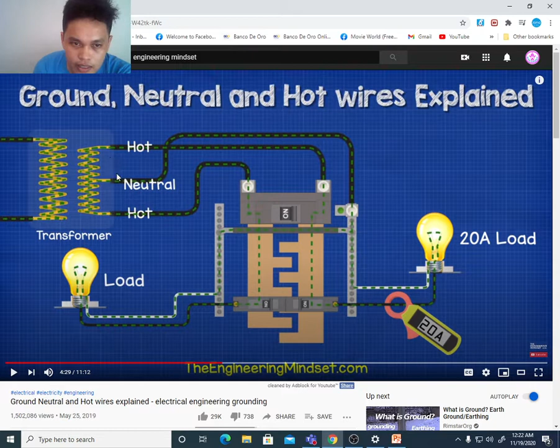Let's say it is, mamaya may example to. So ang purpose ng neutral under normal condition, yung unbalanced current sa kanya magpo-flow. Kung let's say isa lang to, isang hot wire tapos neutral, dito ka lang may load sa side na to. So yung magpo-flow na current pabalik sa neutral, kung ang from dito sa hot wire ang nag-flow is 20 amperes, papaganyan. Yan yung na-reading ng clamp ammeter. So ang babalik din sa neutral is 20 amperes, pabalik din sa source.